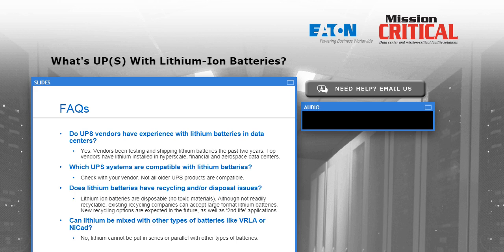One of the things to keep in mind is most of the lithium battery vendors are asking us to return spent batteries to them, because the end of a UPS battery's life is typically defined as when that battery can no longer produce 80% of its original capacity. But in the case of a lithium battery, that doesn't mean the battery is completely useless at that point.